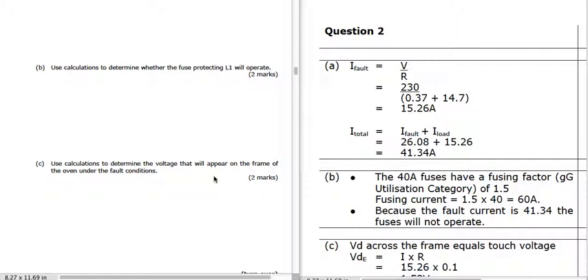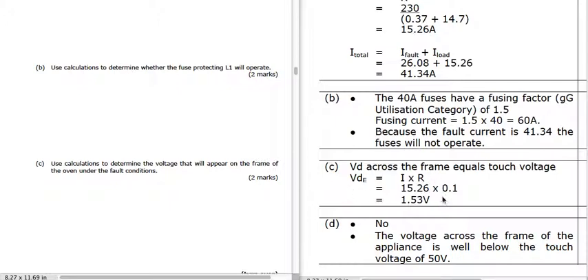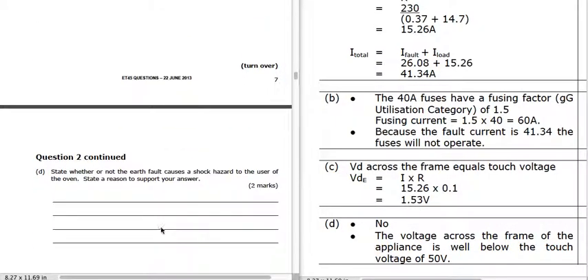To determine the voltage that will appear on the frame of the oven under fault conditions: that current is going to continue to flow, and there'll be volt drops within the system. The volt drop we're interested in is across the frame, and the resistance across the frame is 0.1 Ω. So 15.26 times 0.1 gives us 1.53 volts — a very low voltage. The voltage across the frame of the appliance is well below the touch voltage of 50 volts, so anything less than 50 volts doesn't cause a danger to people.